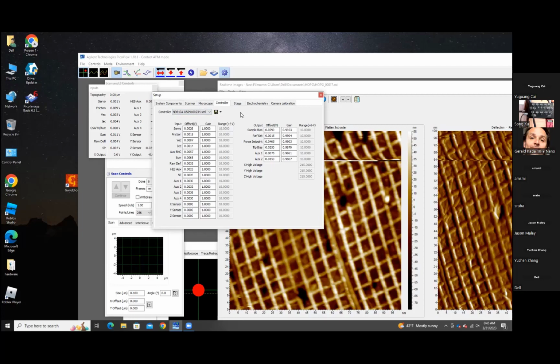It'd be a good idea, Song, for you to go ahead and take a screenshot real quick if you don't want to pause the video later, so that you have these numbers available so that you can reset your calibration file. But the first thing that we would do is set all of the offsets to 0 and all of the gains to 1. All the offset input, right? Offset is 0? On both input and output, you're going to set everything to a default 0, 1 setting. I see. Okay. 0, 0, 0. For your offsets, just do sample bias because we probably won't go through every single one of them. Yes, it's not necessary. We just do one, and also the output, correct? Yeah, just do the sample bias one. Don't worry about the rest of them. So sample bias, offset 0, gain 1. So this is our default starting point.